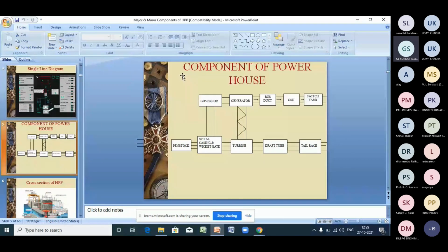They are in a closed loop. That means the governor is responsible for closely monitoring the operation of the turbine generator set. According to the load conditions, your governor adjusts the flow of the water through the wicket gates. More opening of the wicket gates means more water inside the turbine, then more power generation in the generators, and through the generator it is fed to the bus.